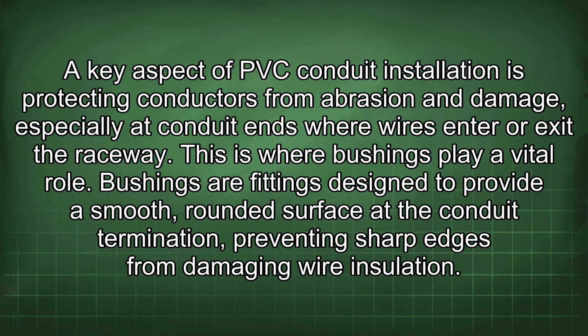A key aspect of PVC conduit installation is protecting conductors from abrasion and damage, especially at conduit ends where wires enter or exit the raceway. This is where bushings play a vital role. Bushings are fittings designed to provide a smooth, rounded surface at the conduit termination, preventing sharp edges from damaging wire insulation.